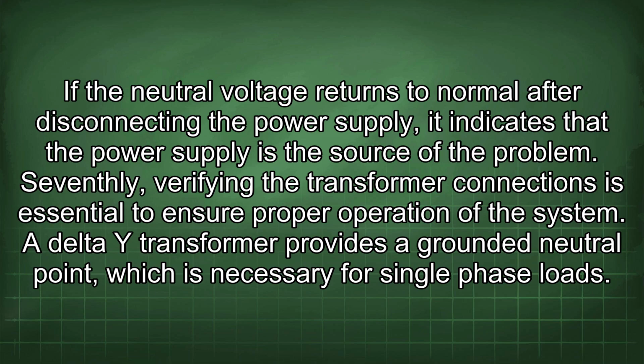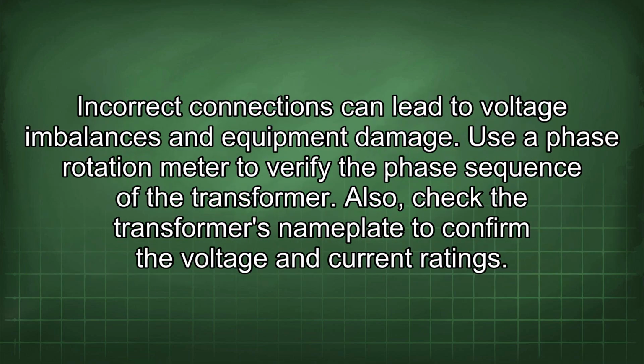source of the problem. Seventhly, verifying the transformer connections is essential to ensure proper operation of the system. A delta Y transformer provides a grounded neutral point, which is necessary for single-phase loads. Incorrect connections can lead to voltage imbalances and equipment damage. Use a phase rotation meter to verify the phase sequence of the transformer. Also, check the transformer's nameplate to confirm the voltage and current ratings.